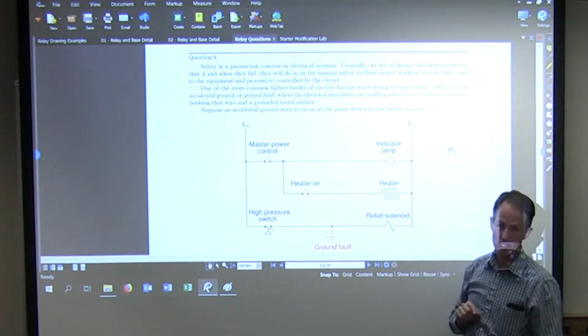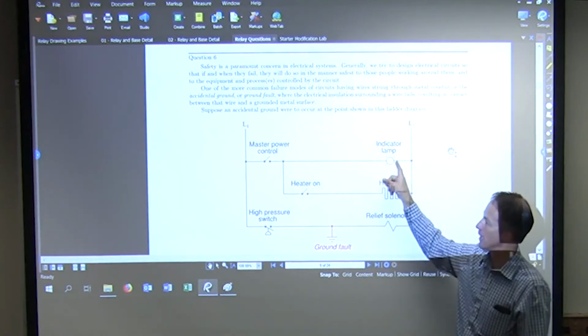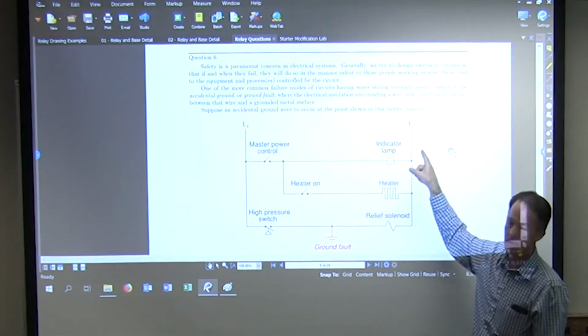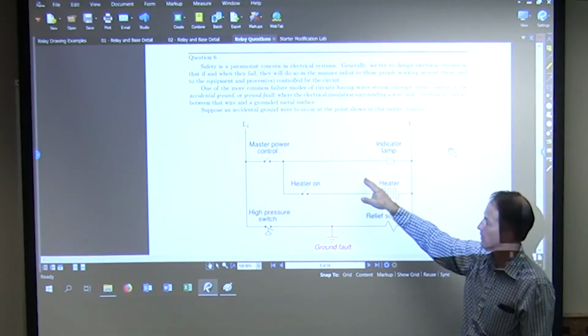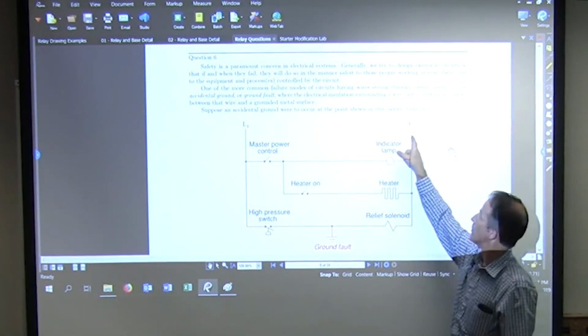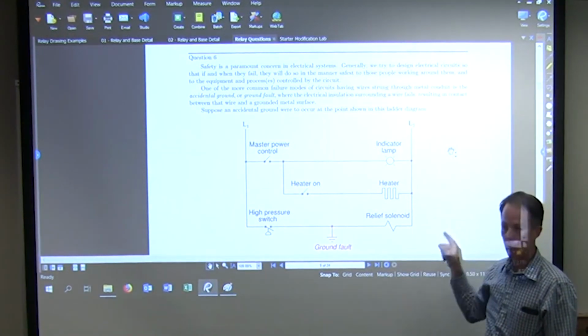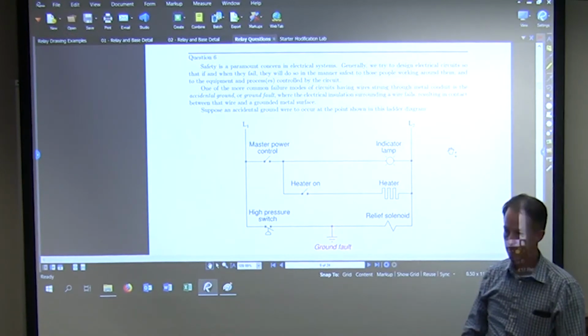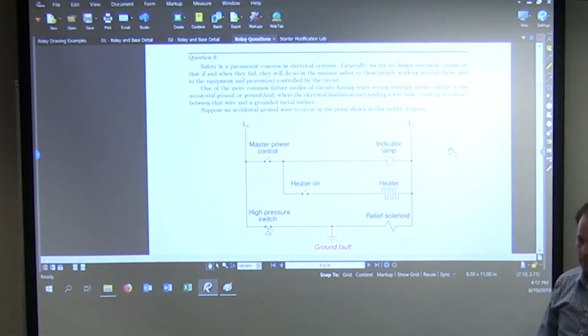The lamp would be the same thing. It's designed for 240 volts. If I only have 110 volts going to ground, so long as it's not directly to ground, it won't trip. That's why the electric motor service that used to be here in town would use a light bulb to test for a grounded motor, because the light bulb itself limits the current, and they could put high voltage on the leads with their test probe and it wouldn't burn it up, without burning up wires or tripping breakers.